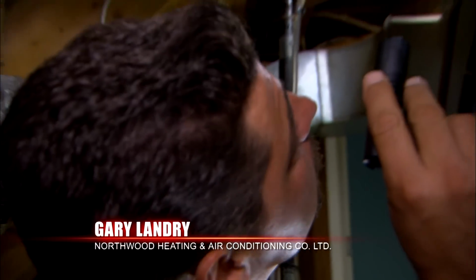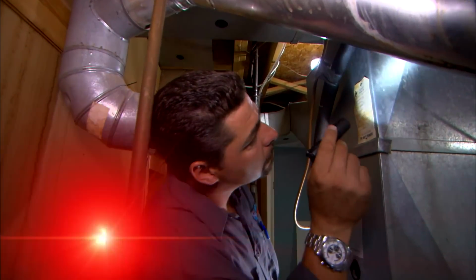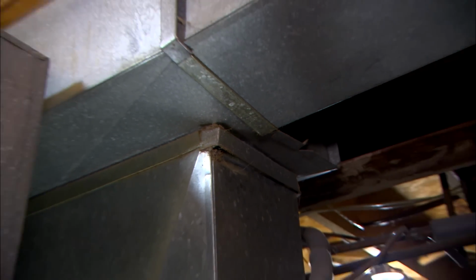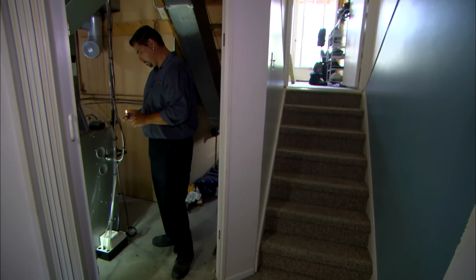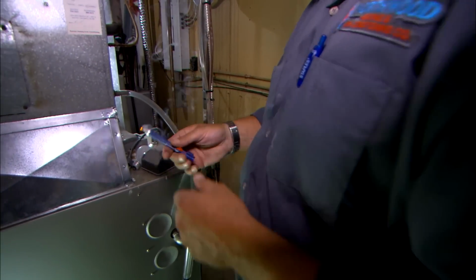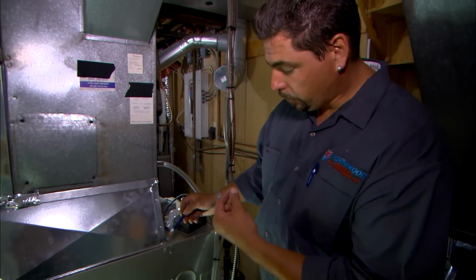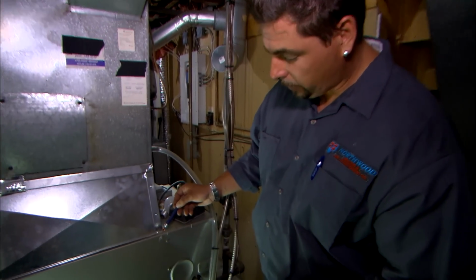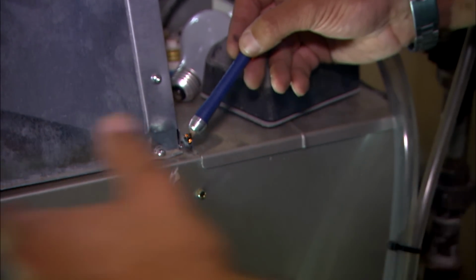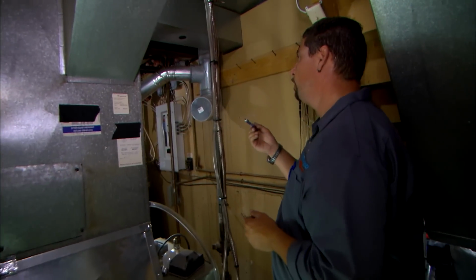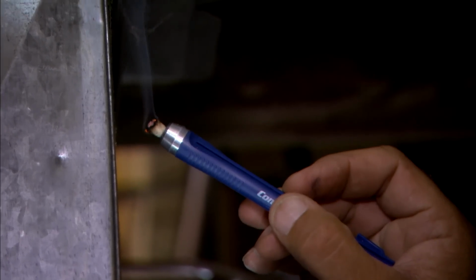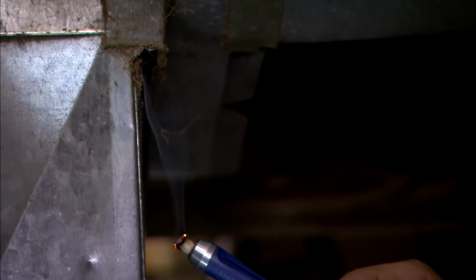A couple of things I'm seeing right off the bat — a very sloppy job, a lot of air leakage. See what this does, it blows smoke — you can see all the air leakage here, all the smoke blowing out, and this is just in the furnace area. Watch the return air itself draw it in — there's a lot of air leakage around this furnace.